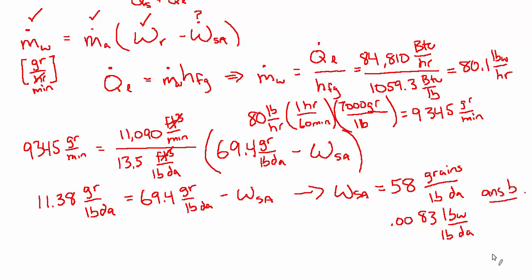And just a note in case you have the original text and you're comparing to the solution worked in the book: you might notice that my numbers for the humidity ratio are just a little bit lower. That's probably because the sensible and latent heat load that I calculate are a bit lower than what they do in the book. They assume that people dancing go for about 1000 BTUs per hour total, and I assume 850. My number is based on the MERM, which is probably a bit more updated than what was available at the time of publication. In any case, we're only talking about a few percent difference, so close enough if it's 58 grains or 60 grains per pound.